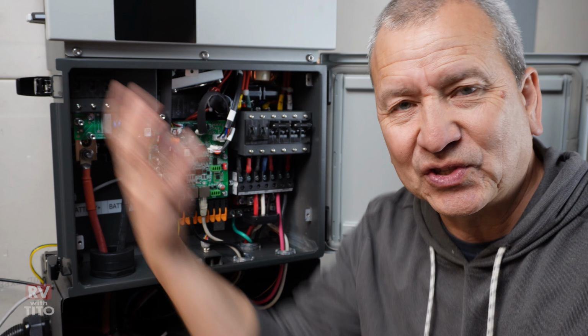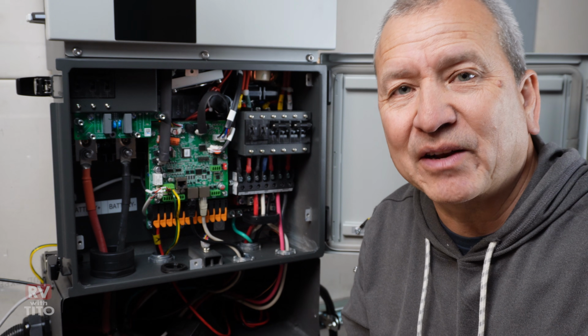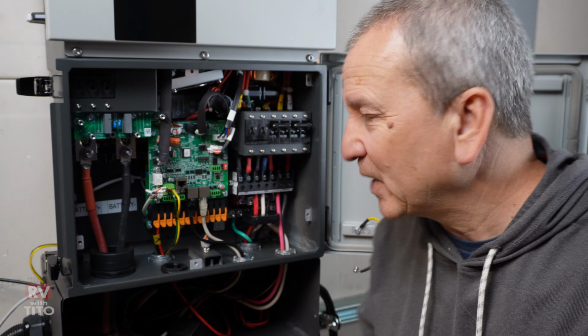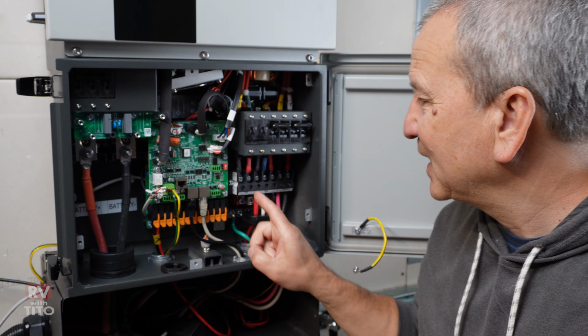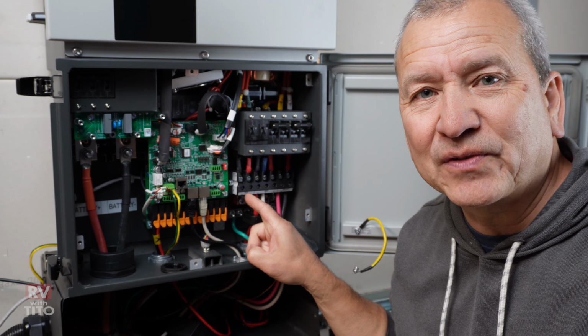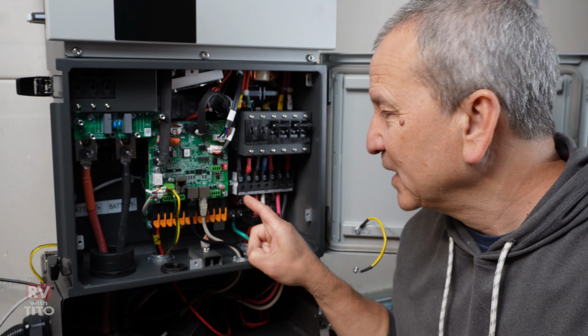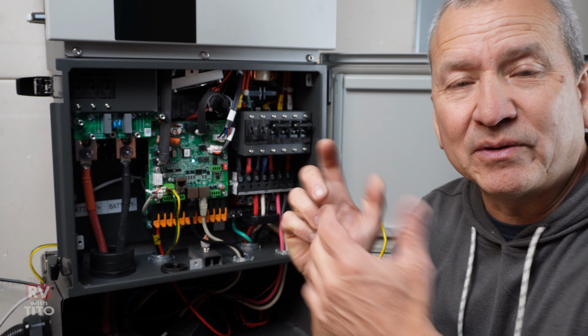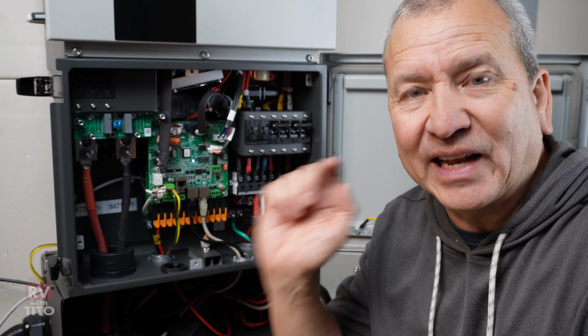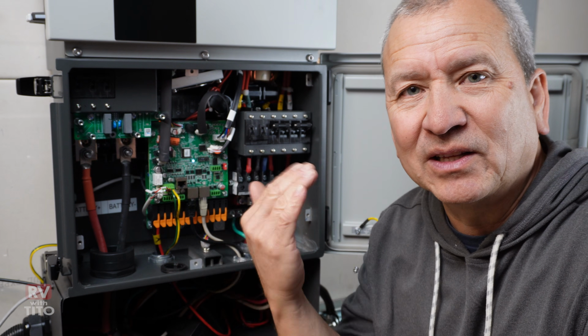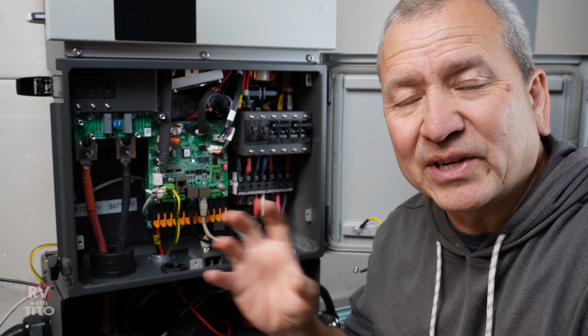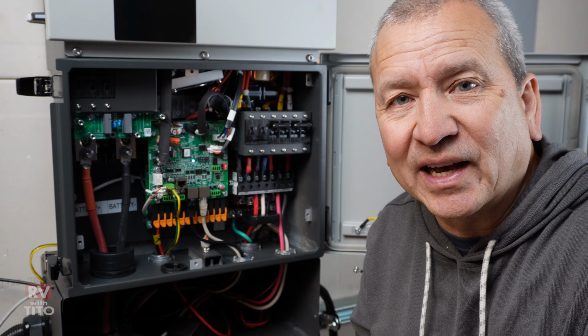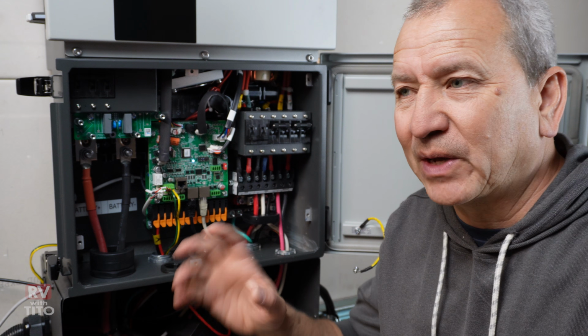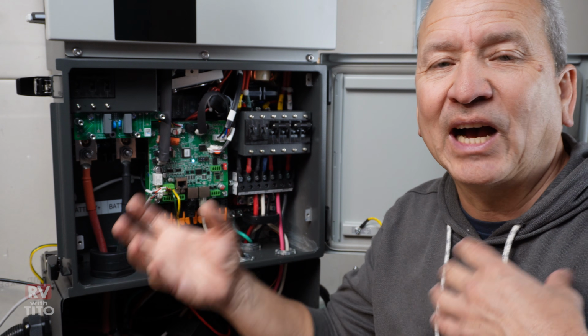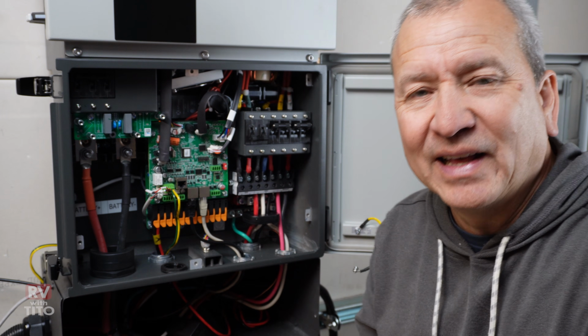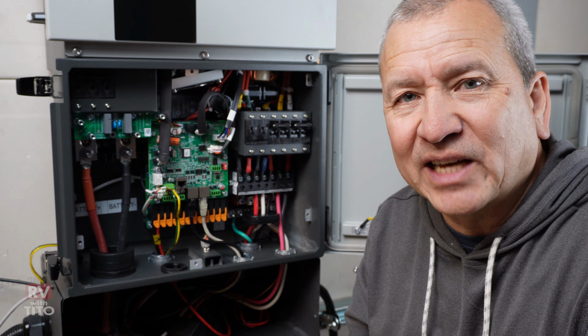If you wanted to use the solar coming in from your grid-tied inverter for something else, you could connect it to here, and it serves as an input at that point. You can go into the settings and enable this feature, and then it'll charge your batteries from your grid tie inverter. And you can set up whether you turn this on and off, how much to charge, and when to charge. You can have all these different settings for that type of setup.